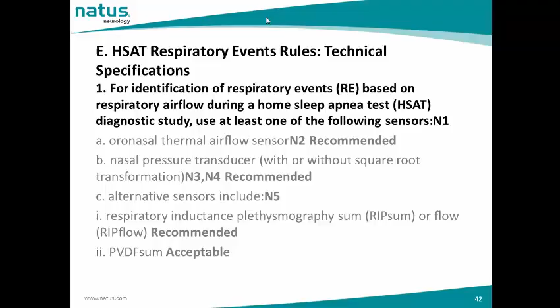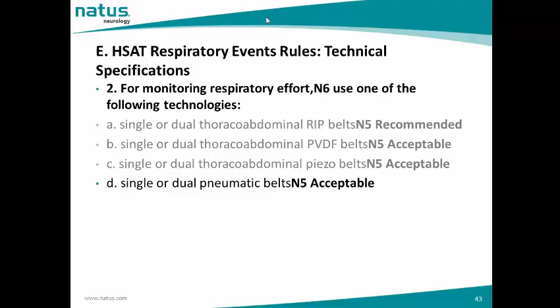For monitoring respiratory effort, use one of the following technologies. Single or dual thoracoabdominal RIP belts, this is recommended, and the acceptable techniques are the PVDF belts, piezo belts, and the pneumatic belts. Single or dual thoracoabdominal PVDF belts, this is acceptable. Single or dual thoracoabdominal piezo belts is acceptable, and single or dual pneumatic belts, which is acceptable.